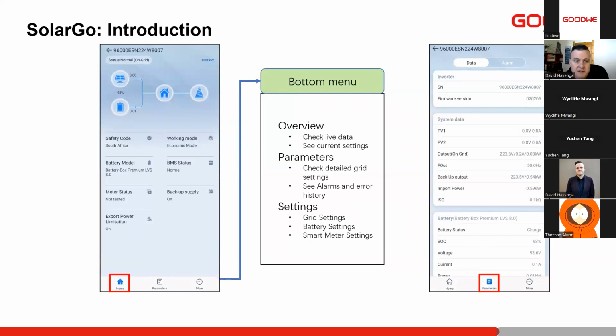Once we connect to it, we'll log into SolarGo. As you'll see here in SolarGo, we've got the bottom menu with home, parameters and more. In the home screen, you've got the overview. You can check the live data at the top in the flow diagram. It also shows some of the current settings: what is the safety code, what is the working mode that's configured, the battery model, the BMS status, meter status, backup supply, and export power limit.